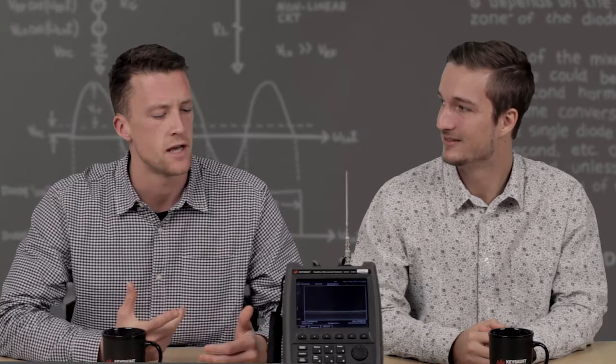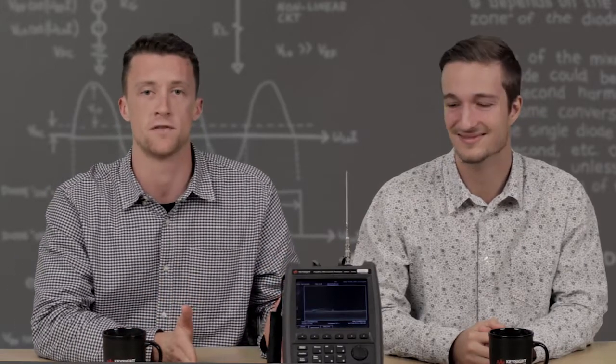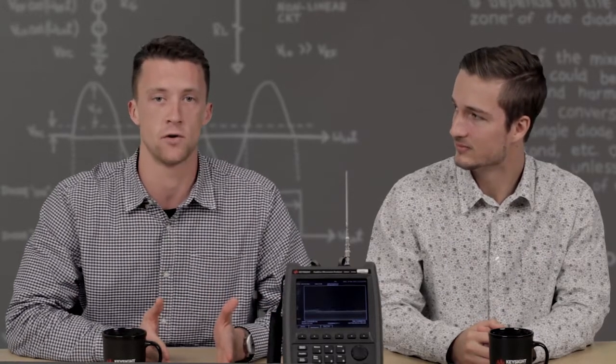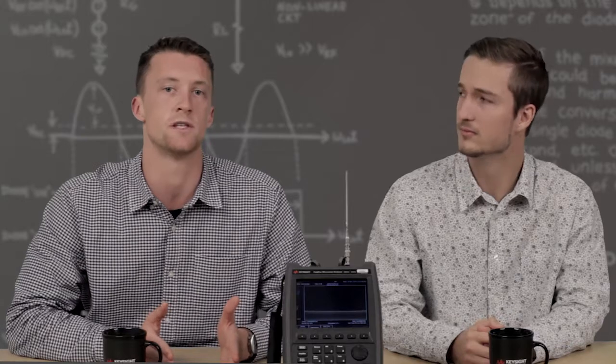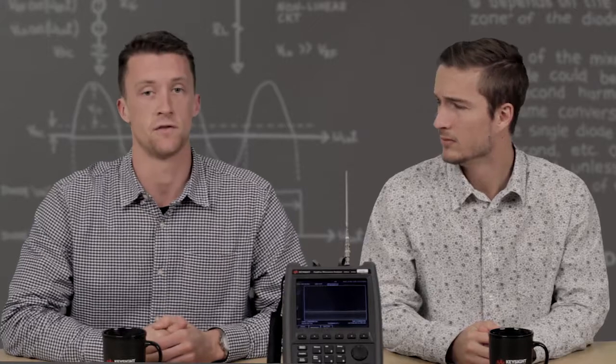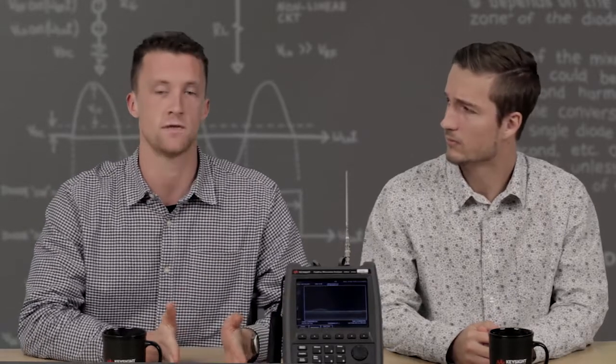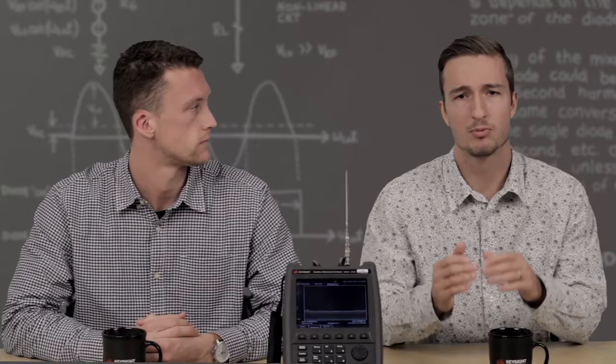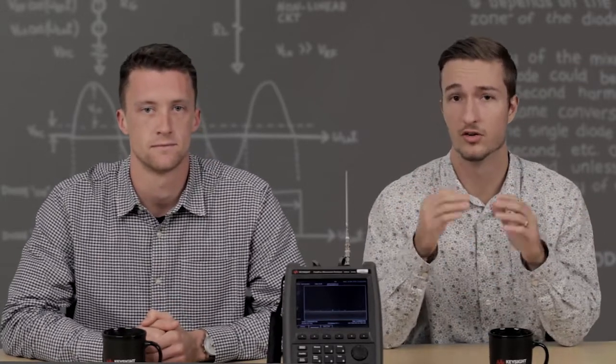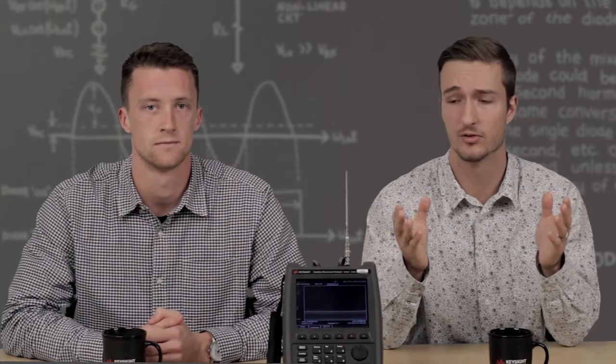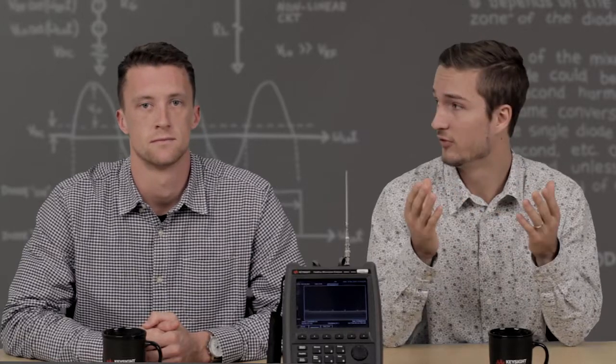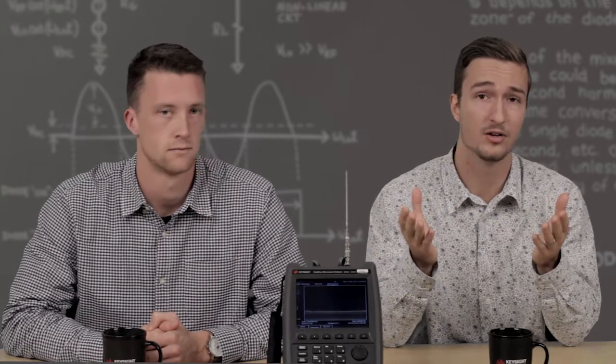In traditional SA mode, the FieldFox is taking measurements for a small period of time and measuring amplitude over time, and then a small period of time after that converting that data through FFT math to a frequency spectrum and putting this onto display. As a result, the FieldFox actually has small periods of time where it's not acquiring any data at all. Problems can occur where if you have a quick pulsing signal or a spectrum that's rapidly changing over time, you can actually miss your signals and not get a full view of the frequency content that you're trying to look for.